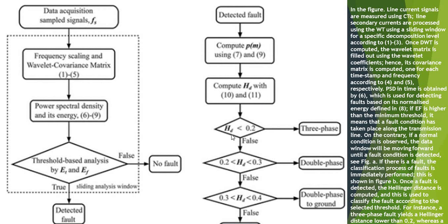So when the Hellinger distance is less than 0.2, it's a 3-phase fault. When the Hellinger distance is between 0.2 and 0.3, it's a double phase fault. When the Hellinger distance is greater than 0.3 but less than 0.4, it's a double phase to ground fault. That's how faults are classified using Hellinger distance.